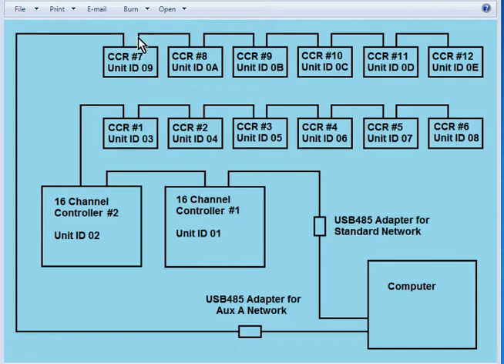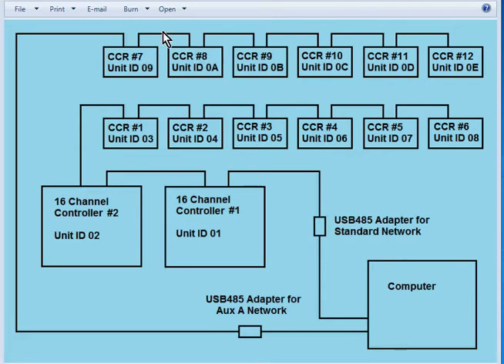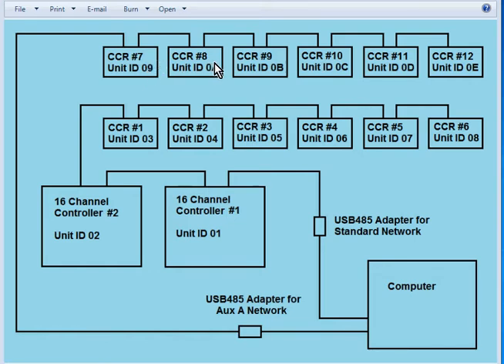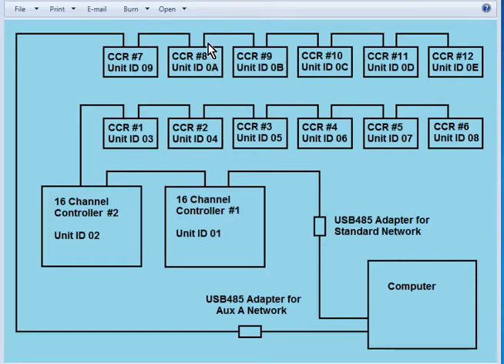And it goes to CCR controller number 7 which has unit ID 09. He is daisy chained to CCR number 8 which has unit ID 0A. Note that the next unit ID after 09 is not 10, it is 0A, and the Superstar software requires that your CCR controllers have consecutive unit IDs, so after 09 you must have 0A.